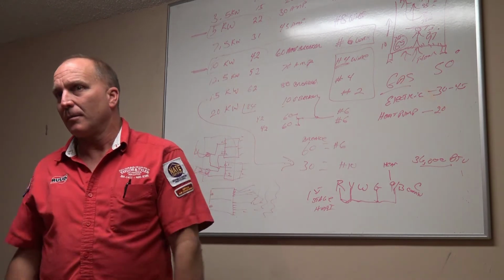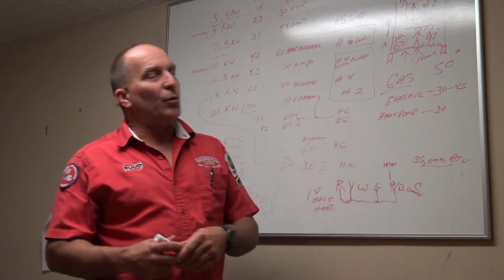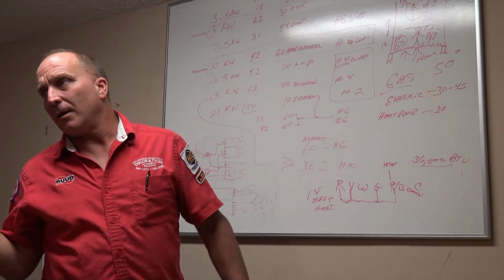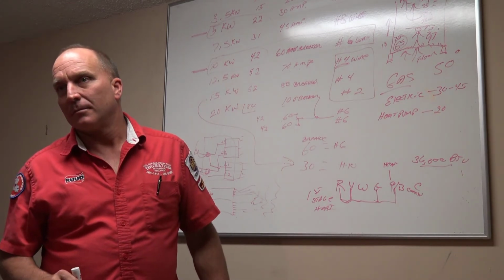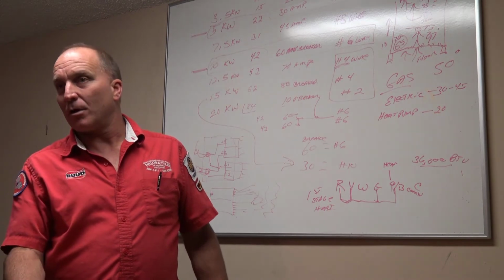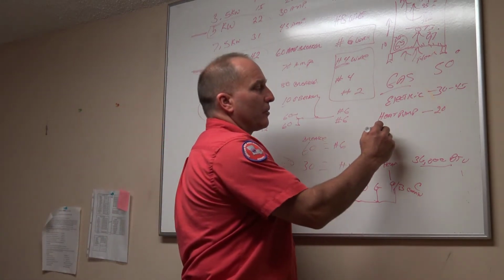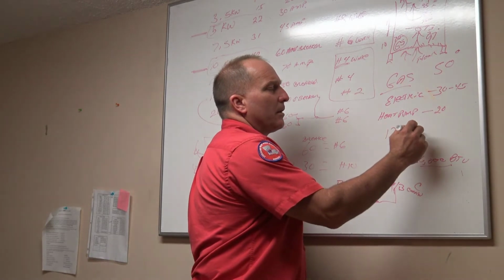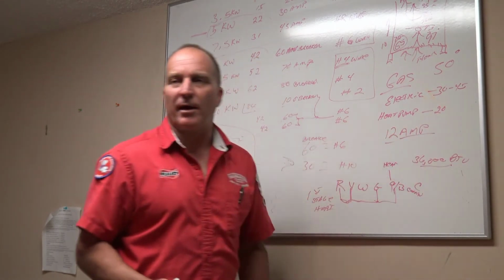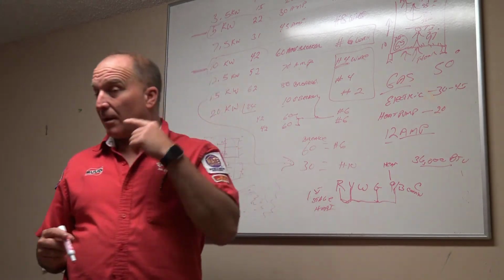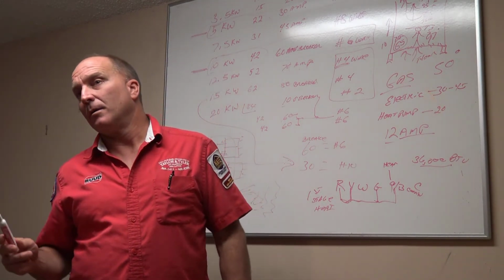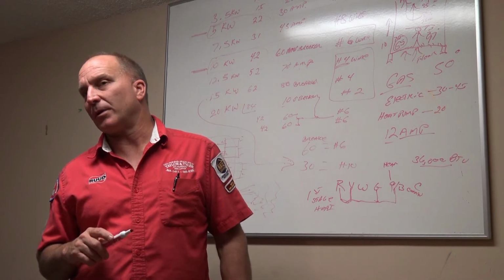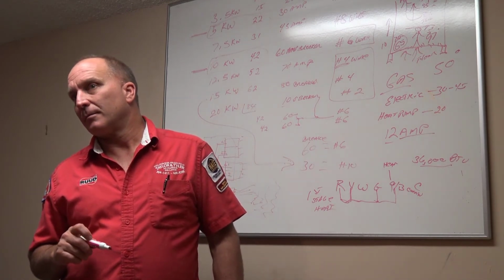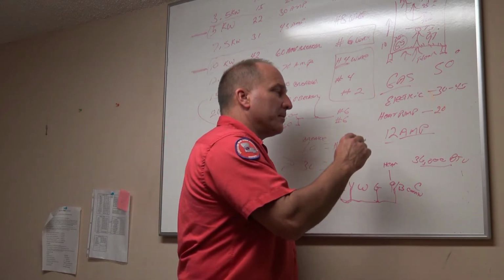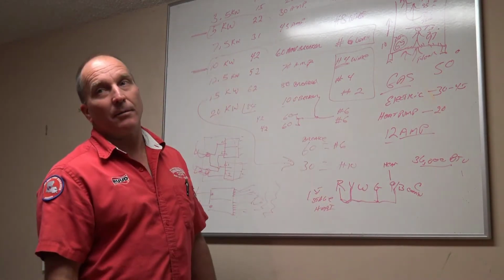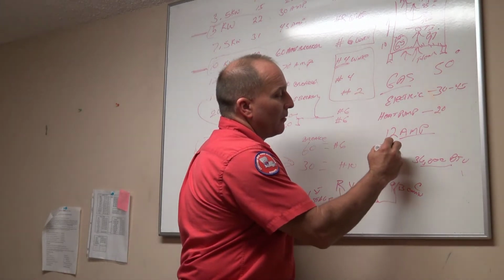I just need it 5 more degrees to make me comfortable. How many amps does this 3-ton heat pump draw in heat pump mode? So you're checking the amperage on your compressor, right? I'm just going to call it 12 amps. Right, wrong, it doesn't matter, I'm just using the number. How many amps does an electric heating element draw for a 3-ton system? What kW would you put that? 10, which is how many amps? 42 amps.